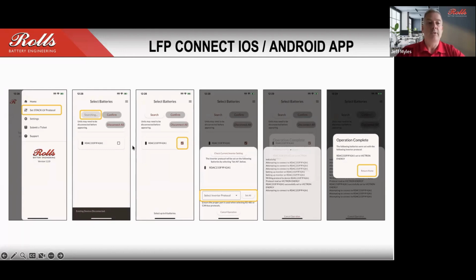Let's say, for example, you had 4 batteries and you wanted to assign the protocol. When you search for batteries within the app, it's going to show you the Bluetooth address for all of those. So what you would want to do is look at the sticker for that primary battery and then select that particular battery from the list of batteries available to connect to. Once you connect to that battery, you can select the appropriate protocol from the drop-down list, which is very similar to the PC software, and then write it. You'll see a status go through while it's sending the information, and then you'll get a confirmation that it has been written to the battery.